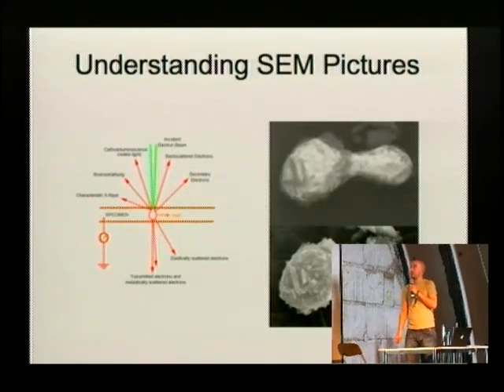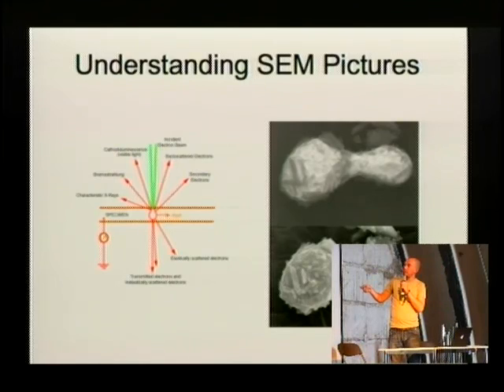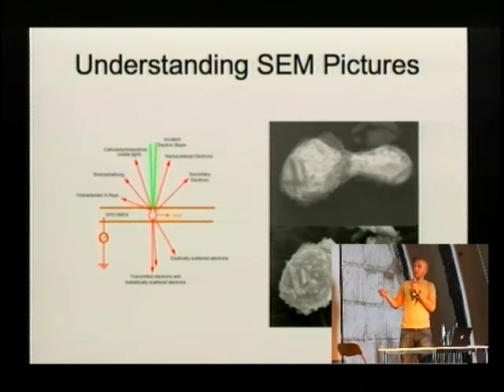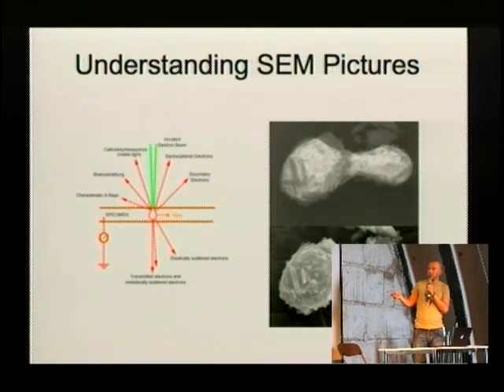So how does this image look, and is there a little bit more to the image than is obvious? It depends a bit on how you collect the electrons that come out of the sample. You have an incident beam of electrons that hits the sample at some point. It's very small, but unfortunately the electrons are not stopped immediately; they continue on and cause several different effects. I will not go into detail too much. You have light coming out, X-ray radiation, and electrons. If you have a thin sample, some electrons just go through, some without even noticing that there's a specimen, others get deflected. But for the scanning electron microscope, the interesting parts are backscattered electrons and secondary electrons.